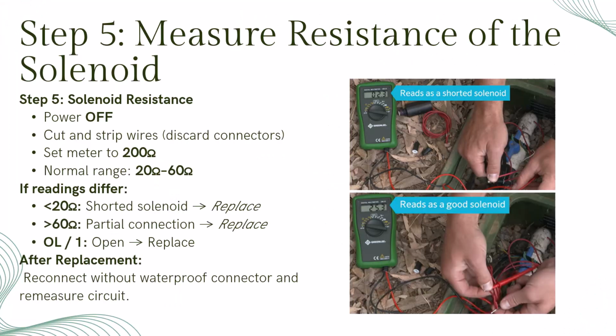The final step is to isolate and test the solenoid by itself. This confirms whether the valve component is the fault or if the problem lies elsewhere in the circuit. Cut the splices, strip the wires, and measure resistance directly across the solenoid leads. If the solenoid reads below 20 ohms, it's shorted. Above 60 ohms, it's partially connected, and OL means it's open. Replace it, retest the circuit, and if the new reading returns to normal, you found your culprit.